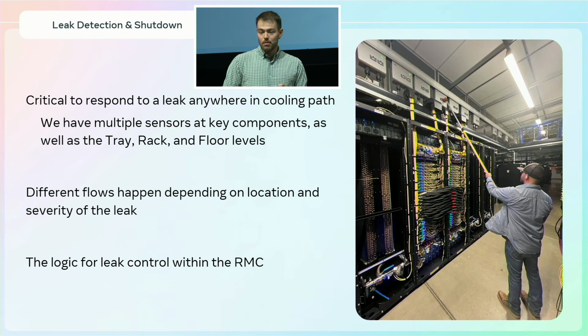We could always just immediately shut off the power the minute we detect any sort of small leak. But this picture here shows that if you shut off the power, the rack is basically completely off until somebody goes to the rack in the data center with a stick, flips all the breakers off, and then flips them back on to reset it.